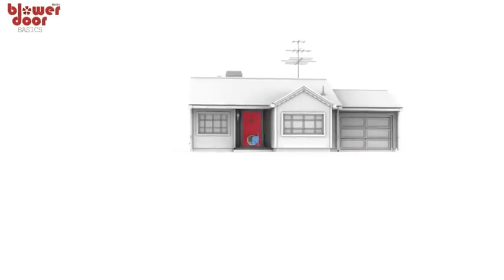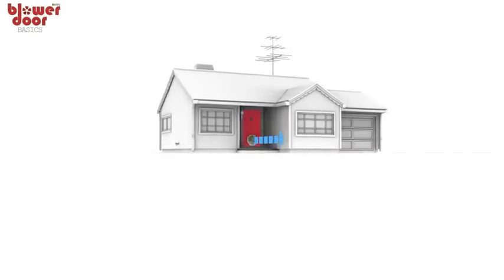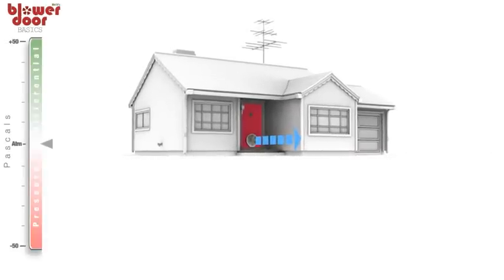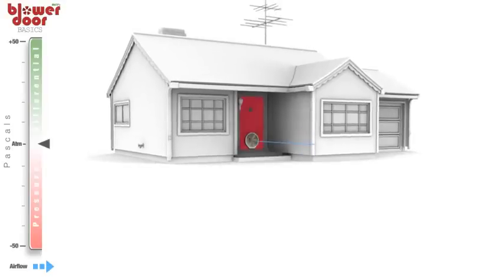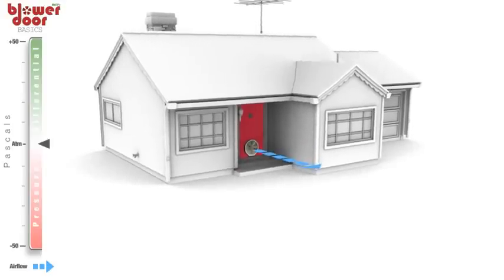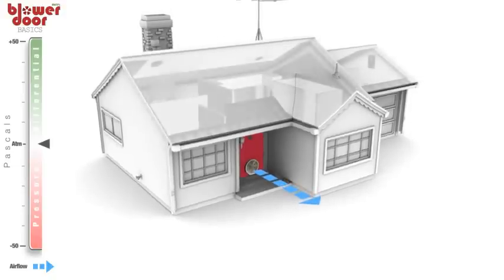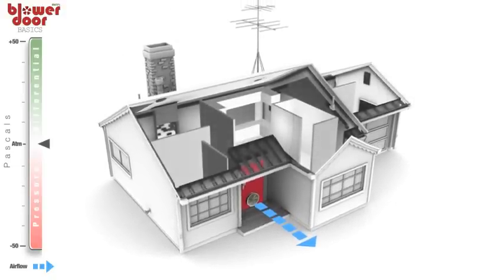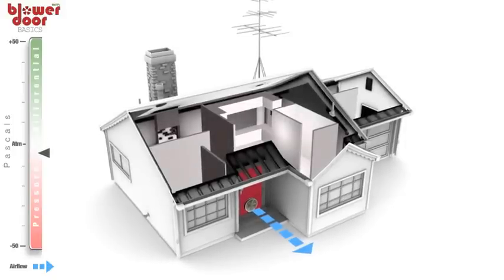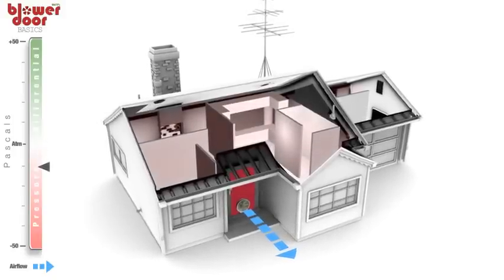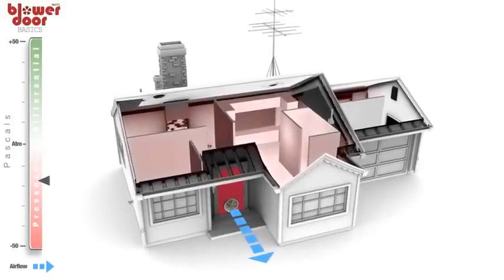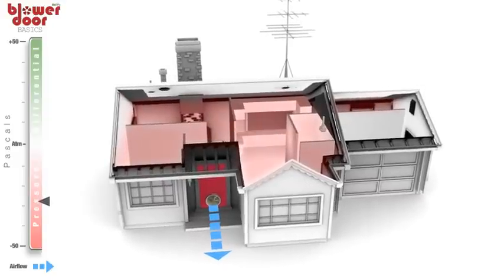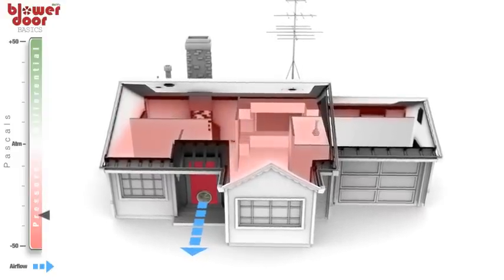When we run a blower door test, air from inside the home is pushed out by the fan, creating a pressure differential between the inside and outside environments. In its natural state, the pressure inside a home is the same as it is outside, right around atmospheric pressure, depending on elevation and the weather. The pressure drops as air exits the front door. We call this negative pressure inside the home: depressurization.